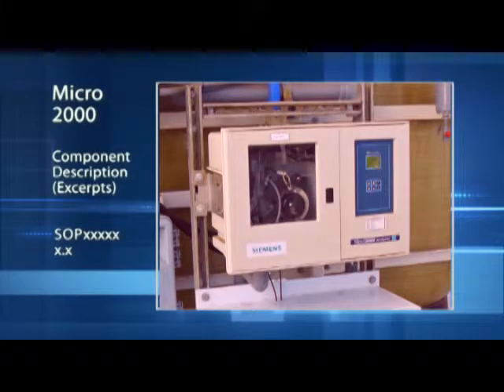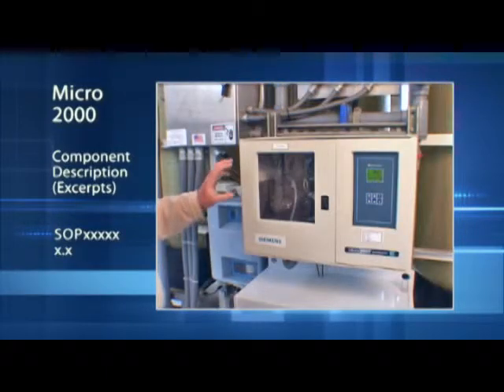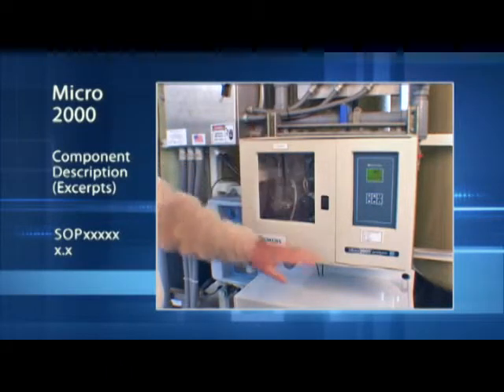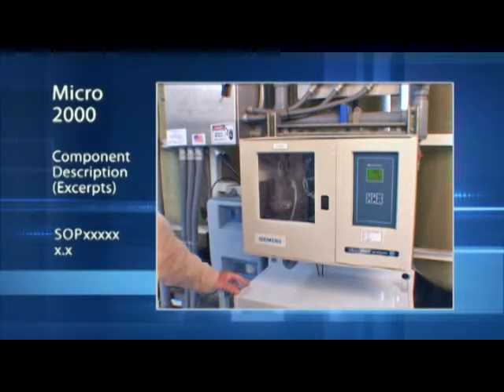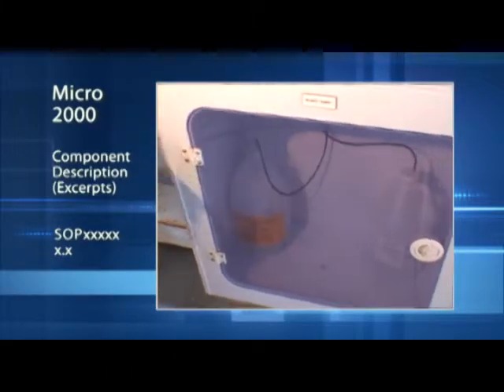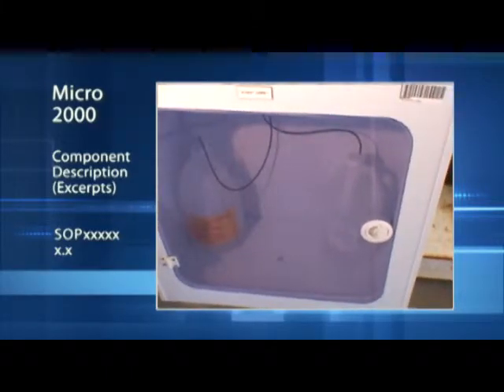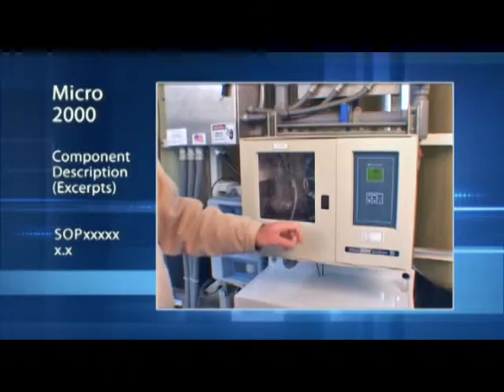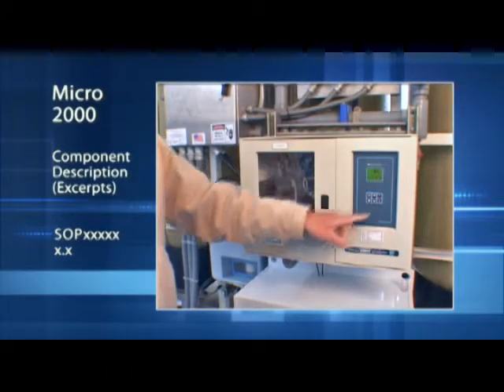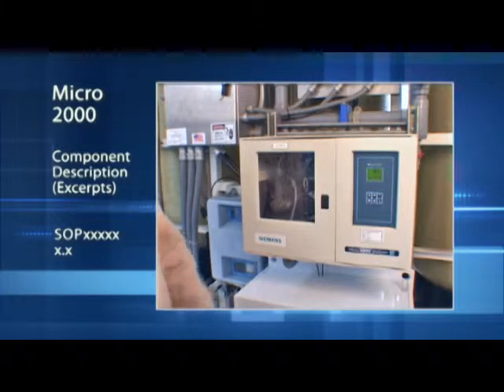So this is the front of the Micro 2000, and we're going to orient ourselves today with the different components inside, which will be used for doing maintenance and calibration. It consists of the analyzer housing itself, and below it is the reagent cabinet, which houses both the pH buffer 4 solution and the potassium iodide mix solution. We have a display screen with the different function buttons on it.